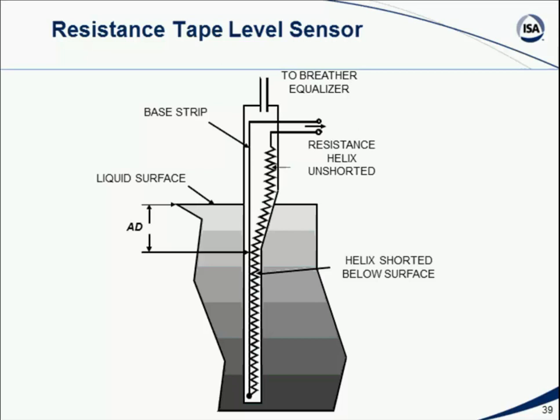So I can calibrate for this. I can put this tape into my tank, raise the fluid level up and down, and make a measurement, and by measuring the resistance through this wire, I can get a rough idea of the tank level. I say rough idea because obviously you have to have a certain amount of increasing tank level before the next bit of tape will short out, so this isn't a high precision measurement, but it does give you more of a continuous indication, for example, than the prior thing where we just used probes of a certain distance in. So we do have the ability to measure resistance based on using a technique like this.